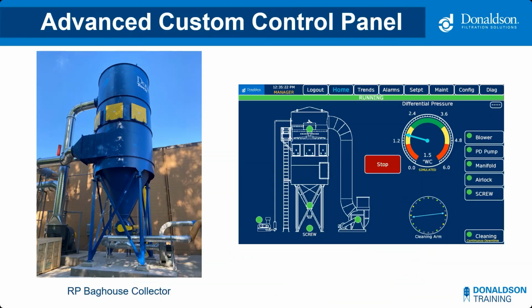Next, we'll look at the advanced ones. Our most advanced control panel includes a larger touchscreen. This interface is incredibly user-friendly. At a glance, you can very quickly distinguish the status of the ancillary components. Here we have a customized view to show a blower, a positive displacement pump, the manifold, rotary airlock, and a screw conveyor. The differential pressure gauge shows the red zones for the alarm levels, the yellow zones for the warning levels, and the green zone for the main operating level. The cleaning arm of the RP collector is also shown on this home page. And speaking of advanced features, I will kick it over to John next.